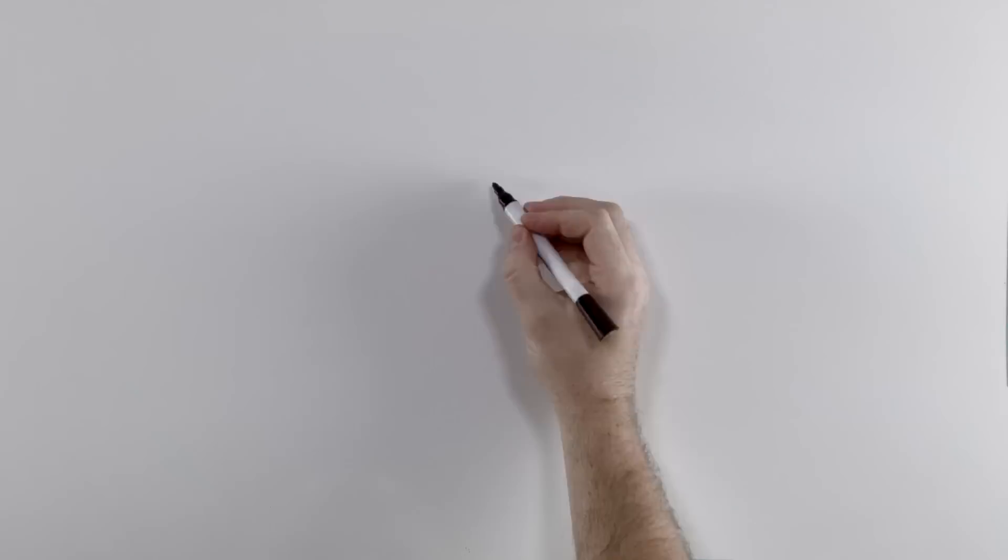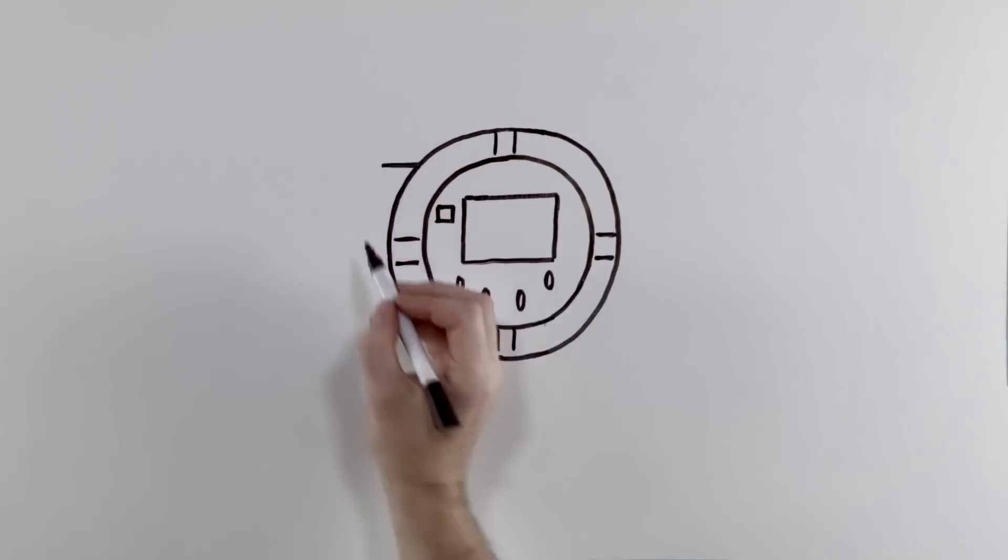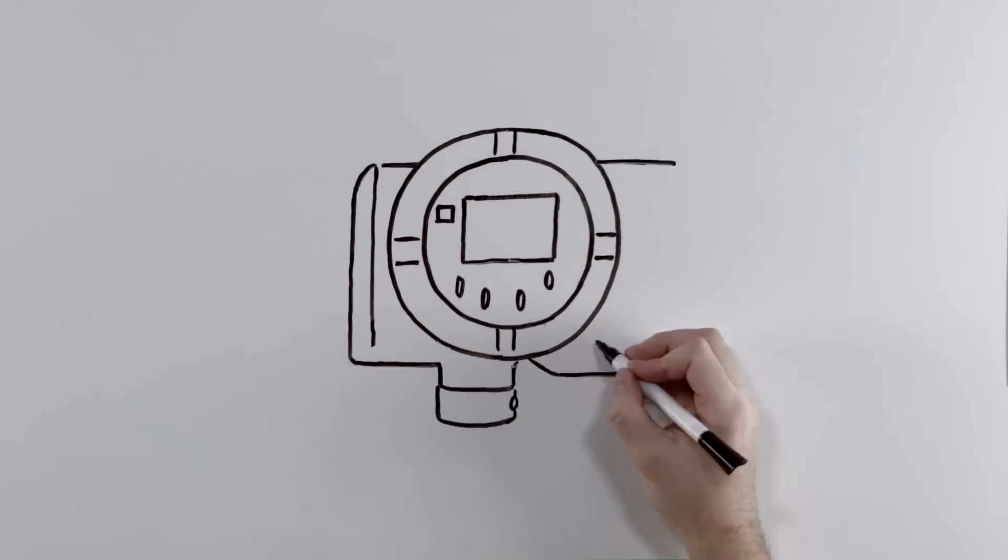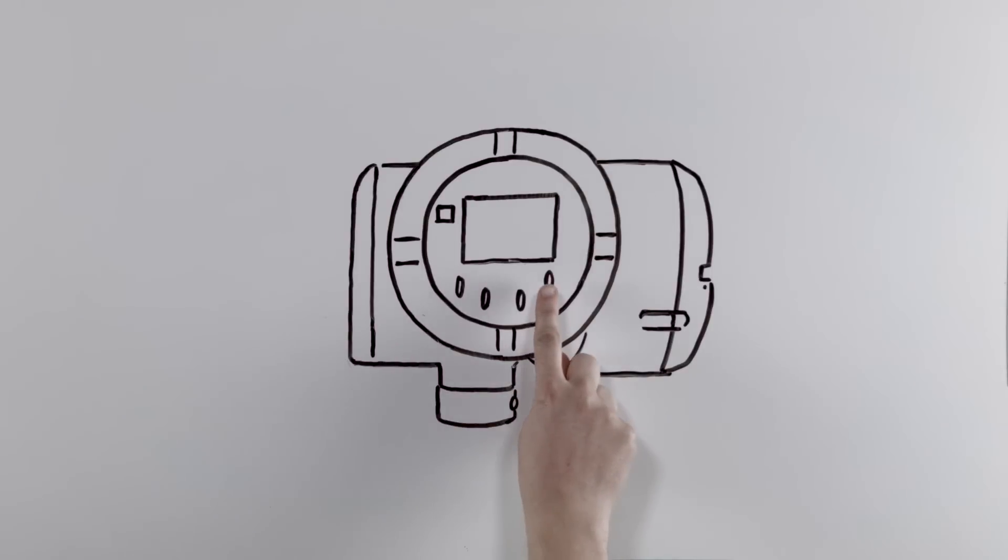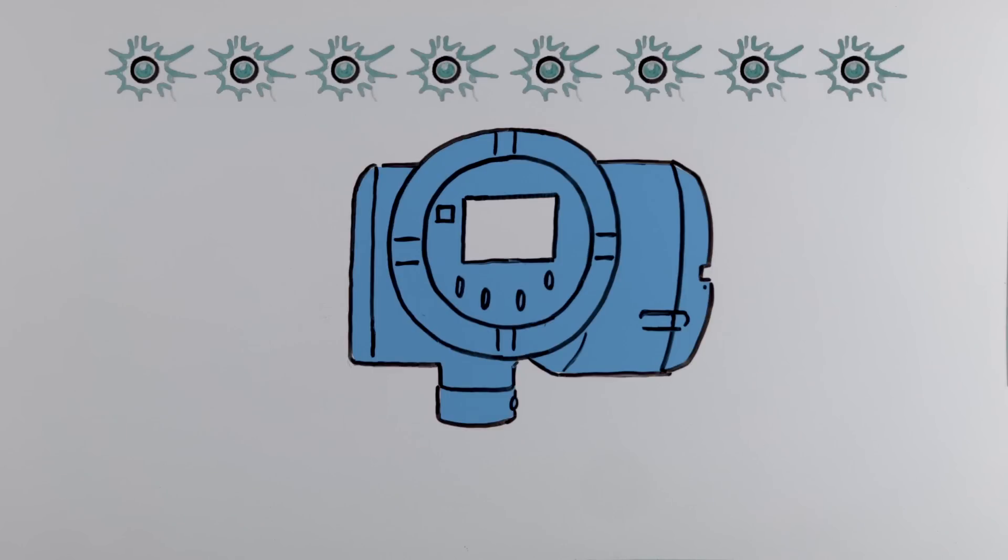And within 20 seconds, with eight simple checks, zero verification determines if your meter zero is within an acceptable range. If zeroing is justified or required, the tool checks to see if process conditions are quiet and stable enough.